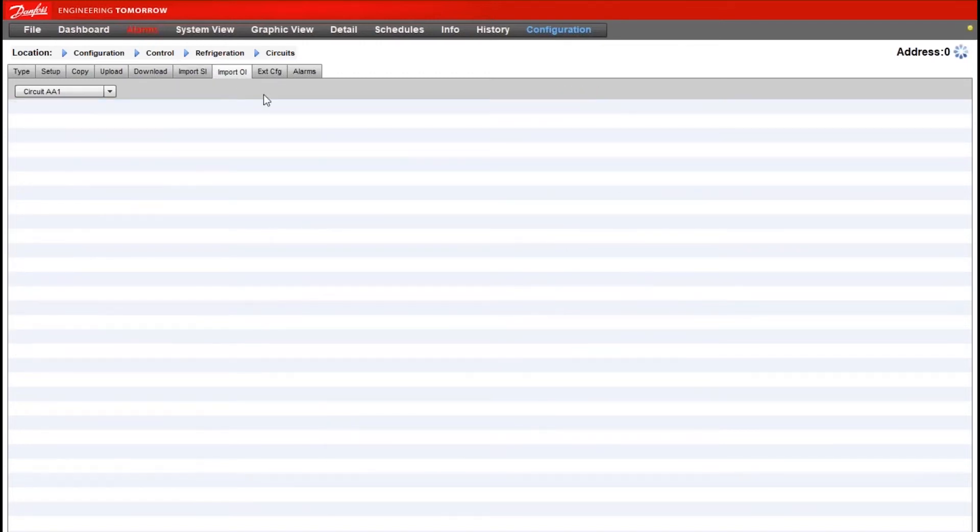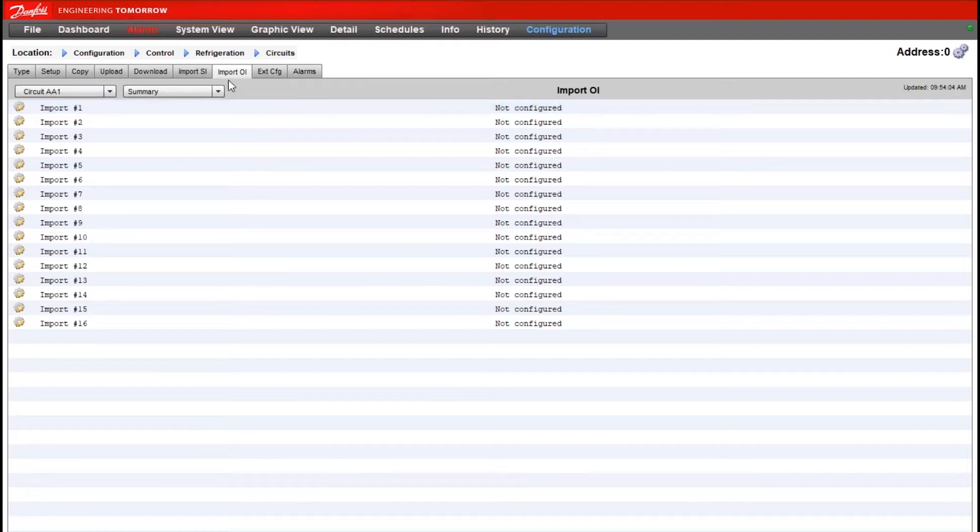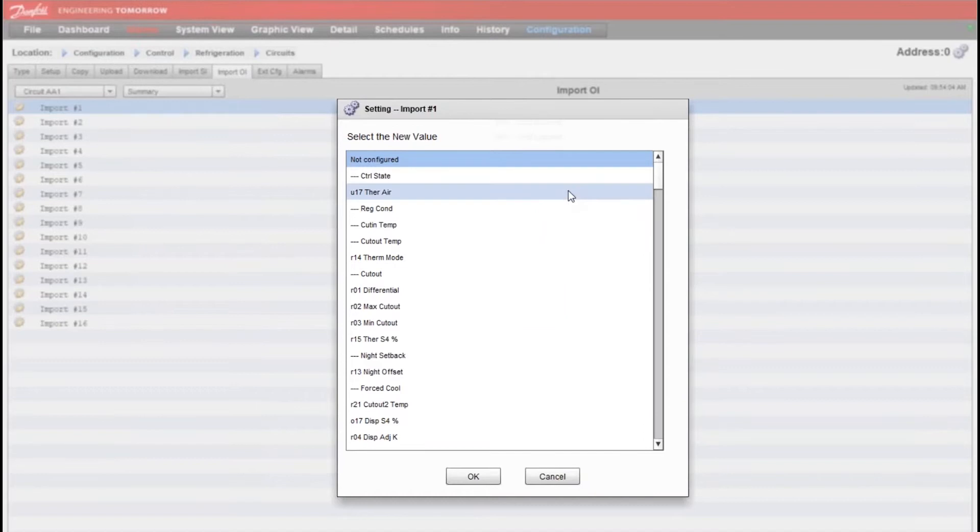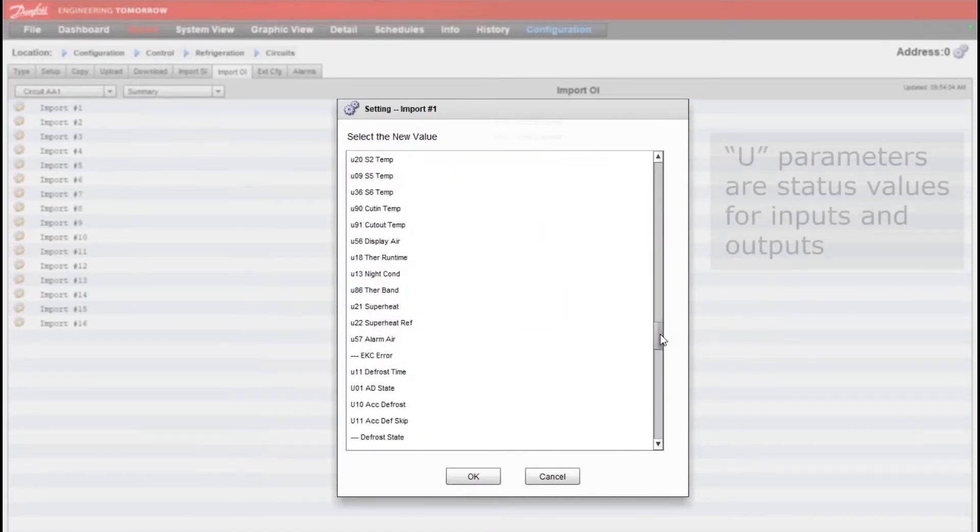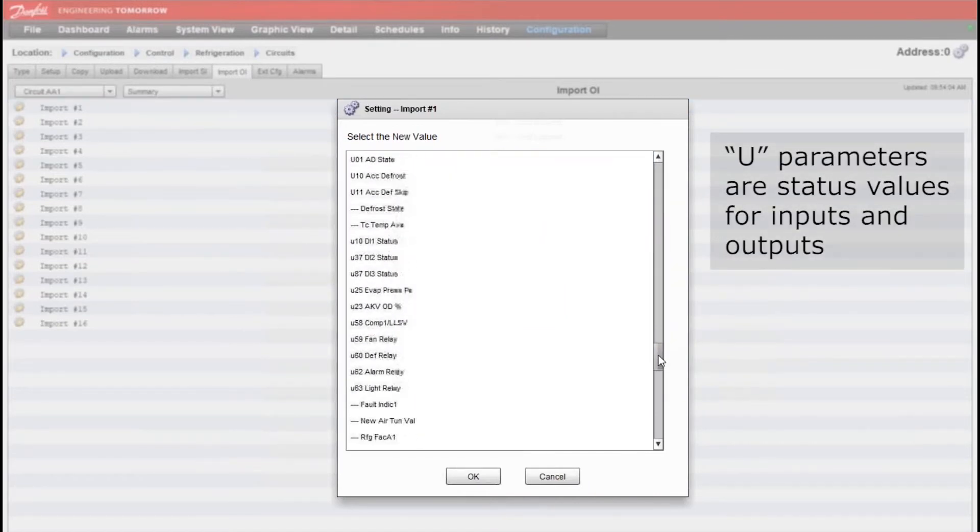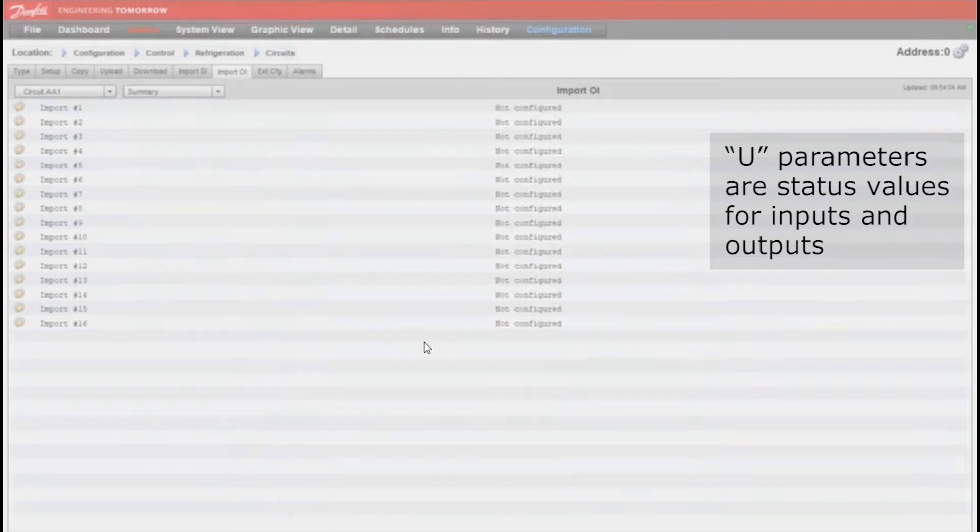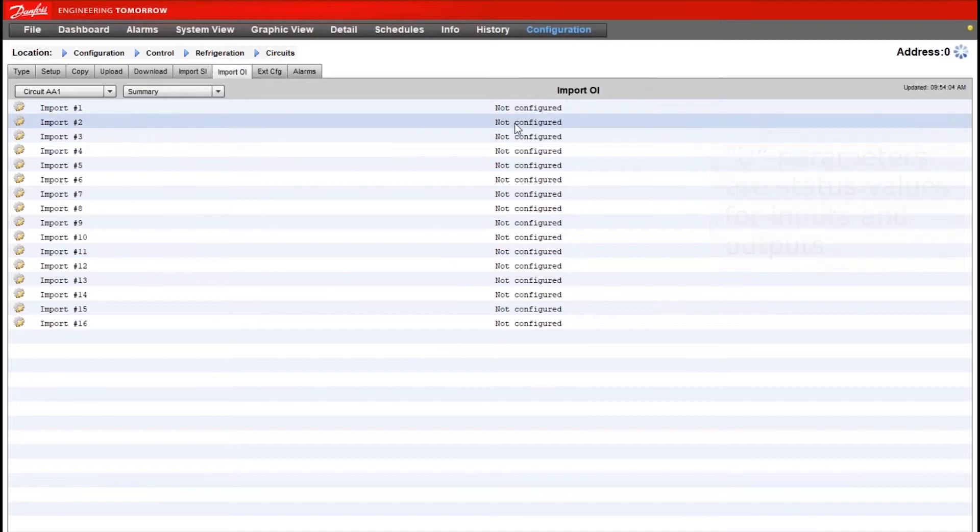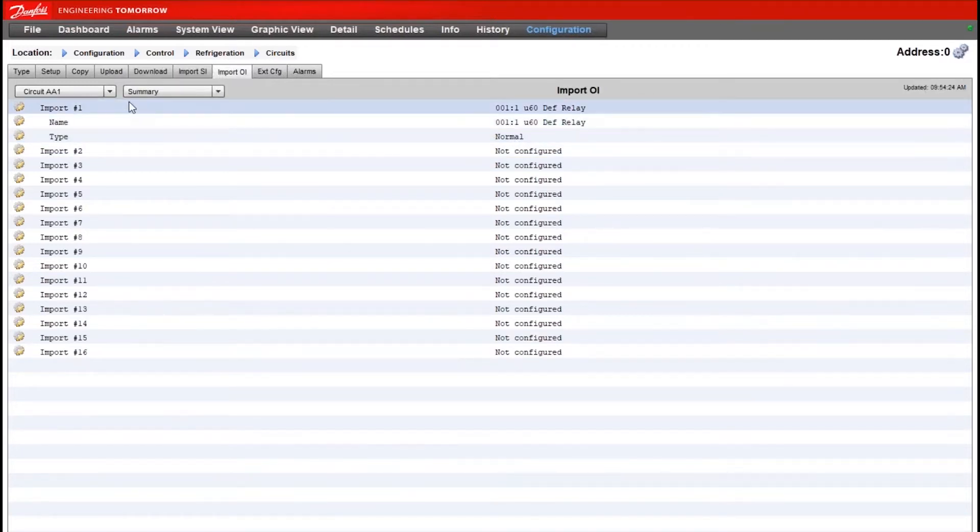For this example though where we're looking at defrost relay status I'll go to import OI. And for the first case controller I'll select import number one. Our U values are always our statuses in the case controller. So here I'll scroll down to U60 for our defrost relay. And I'll import that. Type can be left at normal.